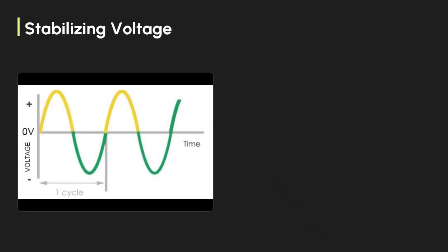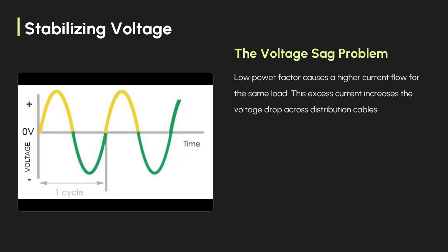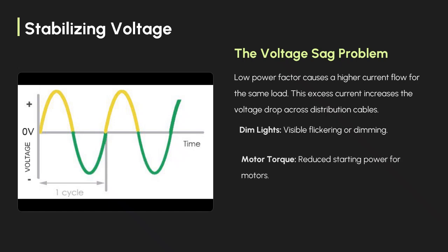Stabilizing voltage. A secondary, but critical, effect of low power factor is poor voltage regulation. The increased current required to compensate for the reactive component leads to higher voltage drops across your distribution cables. This results in voltage sag throughout your facility. This low voltage causes motors to lose starting torque and can cause sensitive electronic controls, common in modern manufacturing, to operate erratically or even reset and fail.